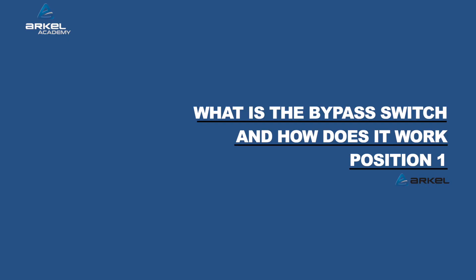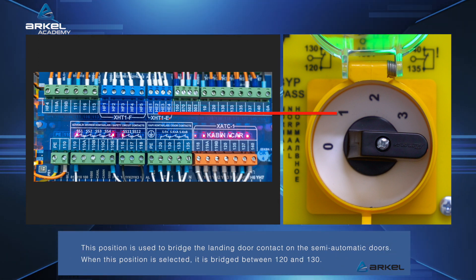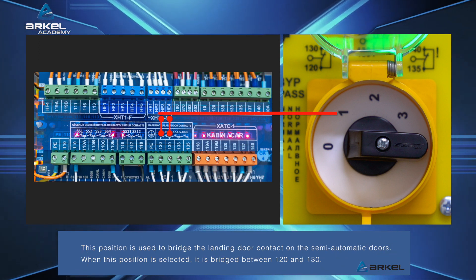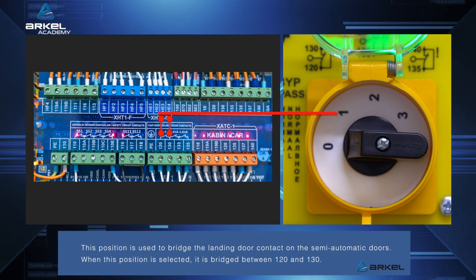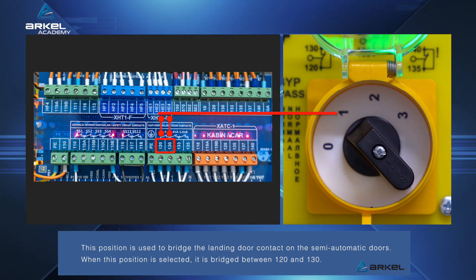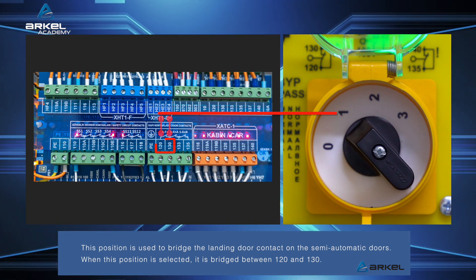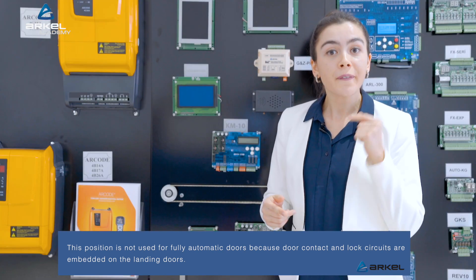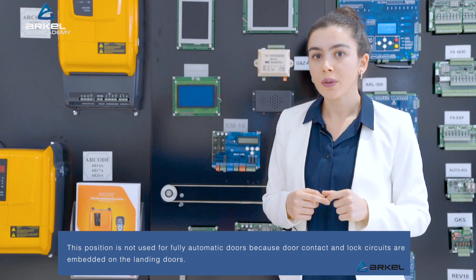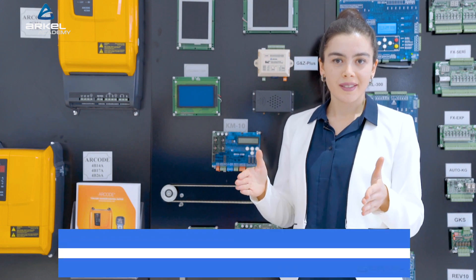Position 1: this position is used to bridge the landing door contact on the semi-automatic doors. When this position is selected, it is bridged between 120 and 130. This position is not used for fully automatic doors because door contact and lock circuits are embedded on the landing doors.